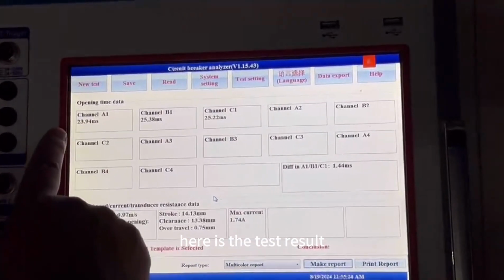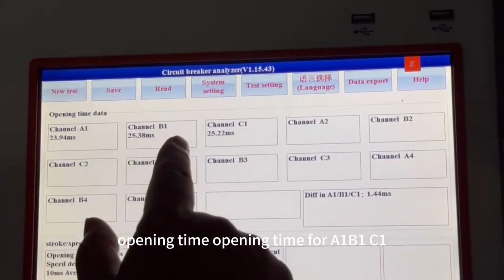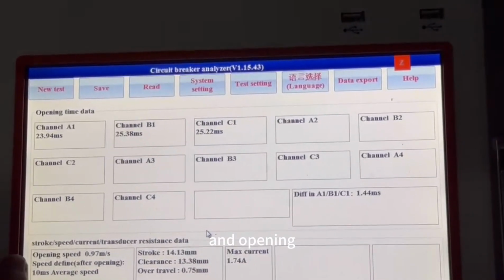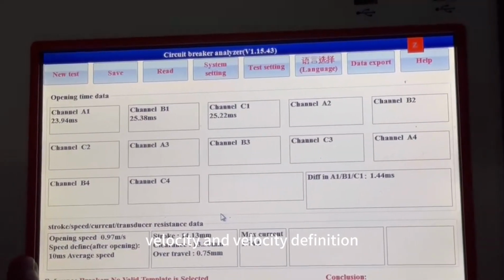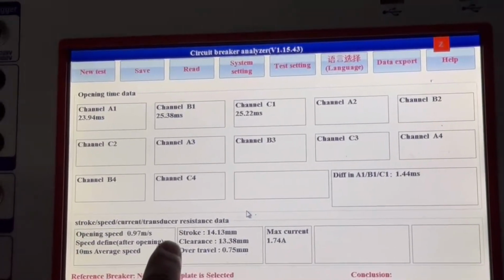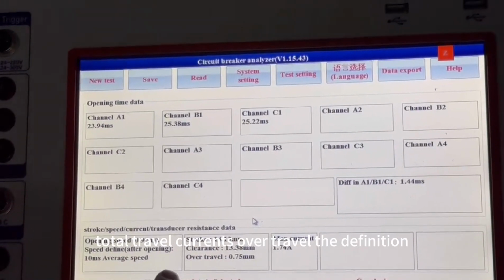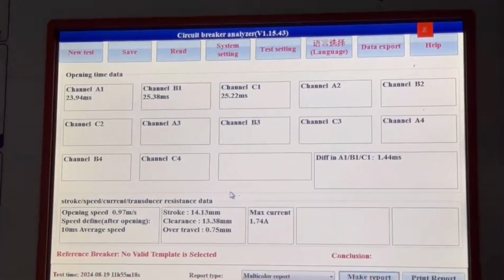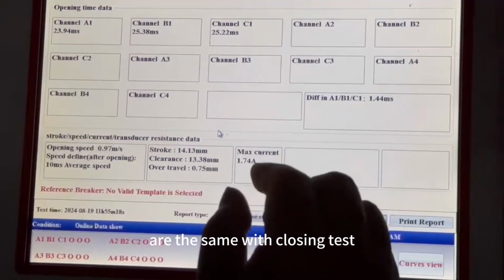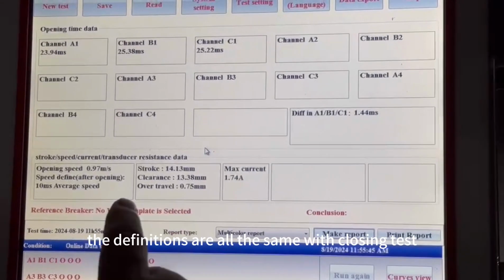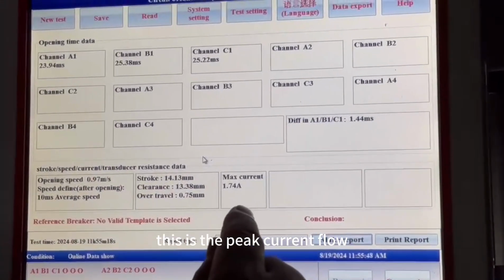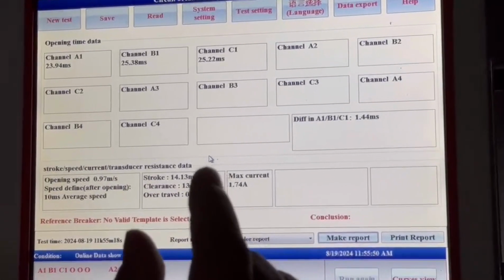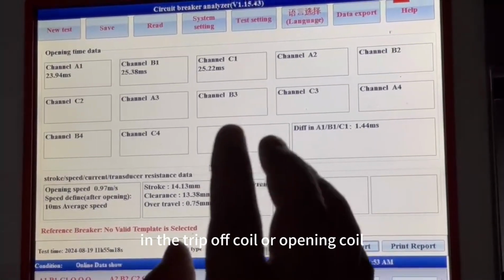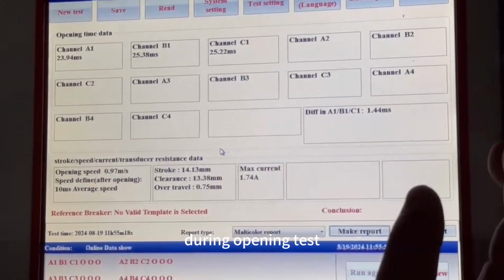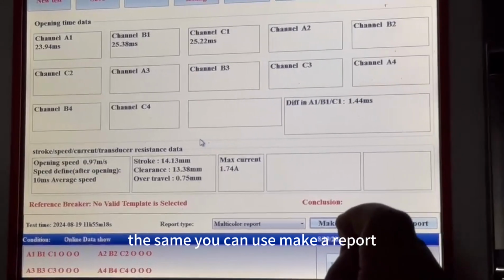Here is the test result. Opening time for A1B1C1, and opening velocity and velocity definition. Total travel and over travel, the definitions are the same as the closing test. Maximum current, the definition is also the same as the closing test. This is the peak current flowing in the trip off coil or opening coil during the opening test. The same, you can make a report, a Word report, for the trip off test.